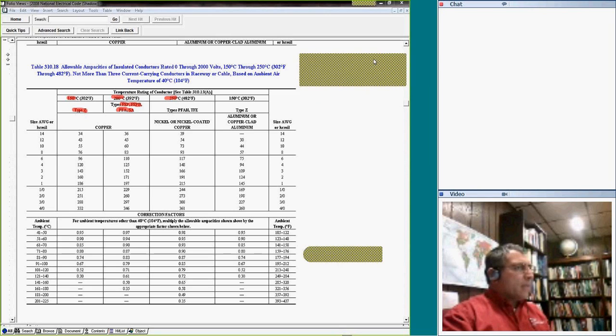These are used in places, guys, where the ambient temperature is extremely hot. So look at this. It's the allowable ampacity for insulated conductors up to this voltage, in an ambient temperature of 40, with insulation rated from 150 all the way to 250. There should be no more than 3 current-carrying conductors in a raceway, a cable, or in the air. Look at the temperature, it's 40. So based on this one, we don't have 500. They don't make it for 500.